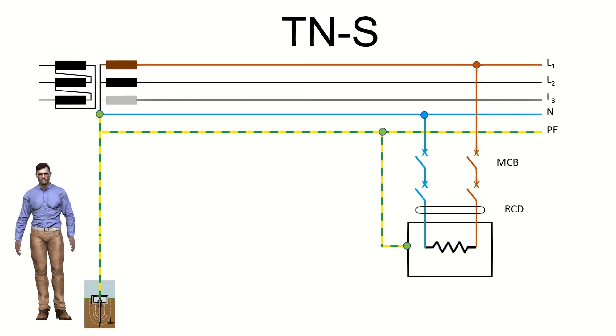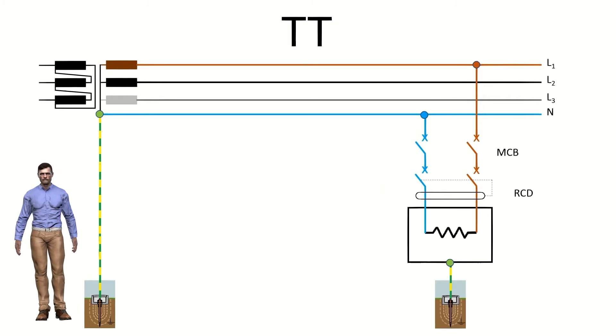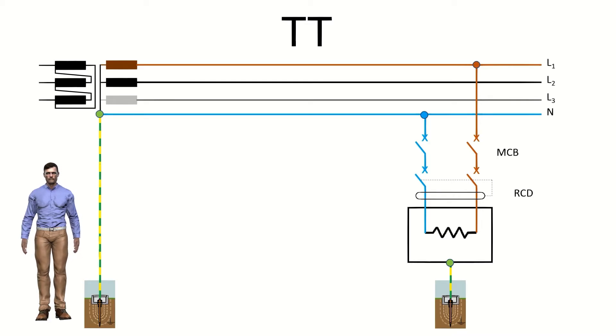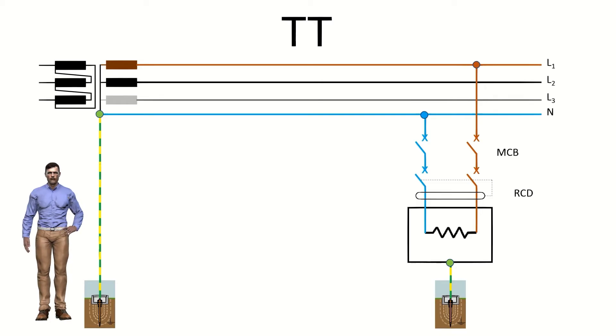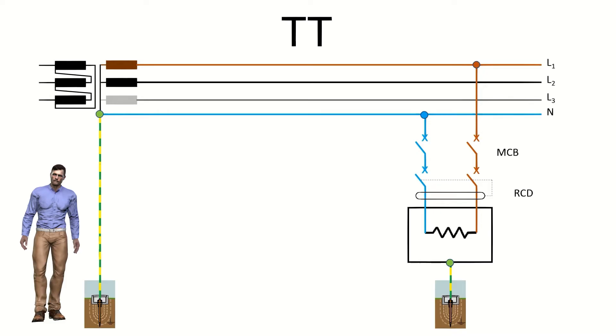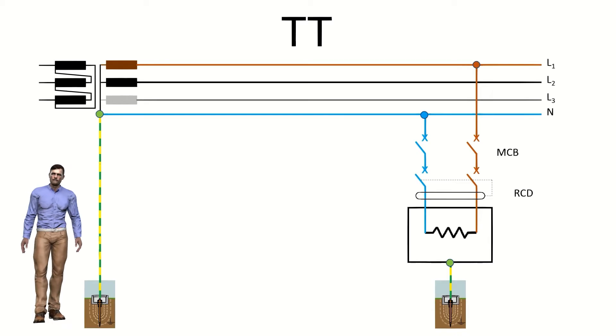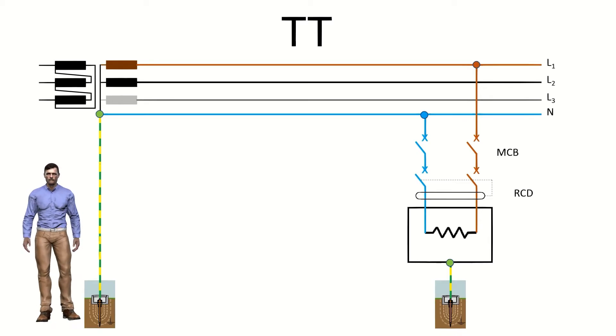In a TT scheme, both the power supply and the masses of the receiving loads are connected to earth directly, but they are different earths — for example, the transformer earth of the transformation center and the ground of our house. These grounds are physically and electrically separated and use different stakes. In this type of scheme we will find two types of protections at a functional level: on the one hand, protections against overcurrents and short circuits, and on the other hand, differential protections. These two protection functions may be physically implemented either in a single element or in two separate elements.